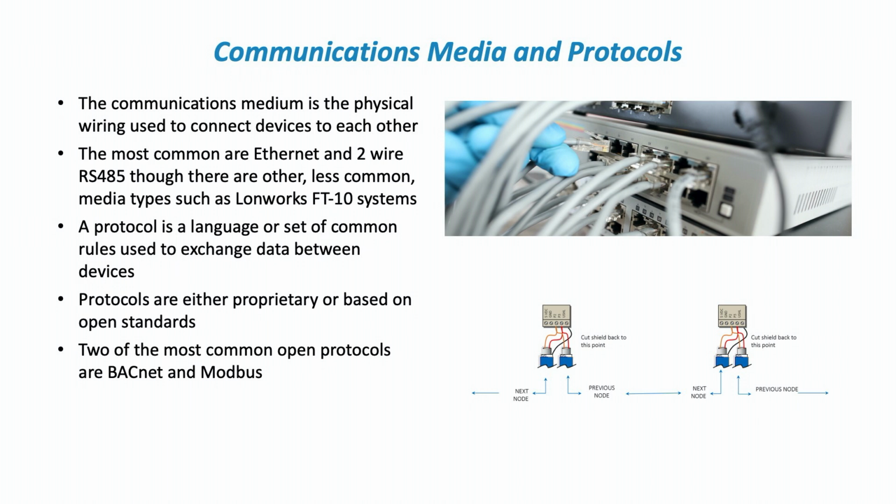Protocols are either proprietary or they are based on open standards. The thinking has traditionally always been towards proprietary protocols, and the reason that manufacturers wanted to do this was it got vendor tie-in. If you had your own protocol, you would sell your BeMS to a client, they would put it in the building, and you couldn't use anyone else's controller in there. But of course, the opposite argument is that the building next door has got your rival's equipment in it, and now we can't put any of your equipment in it. So gradually, people came around to the idea of using open protocols. A lot of client pressure was put onto manufacturers to make this transition, because obviously it benefits the end users most.